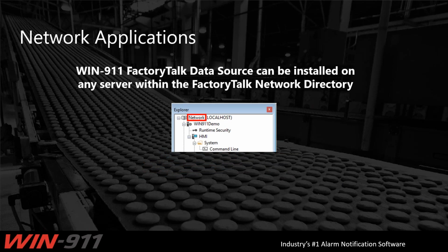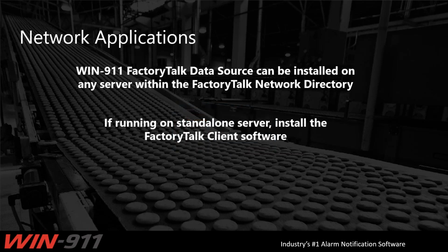If you install WIN-911 on a standalone server, so you install WIN-911 by itself without the FactoryTalk software there, what you're going to want to do is install the FactoryTalk client software on this machine, because it puts all the backend services that we need to communicate with an alarm and event server on that machine. You also need it there to join the directory anyway. So when you are running WIN-911 on a standalone server, you need to join that FactoryTalk directory. Installing the FactoryTalk client software is just the quickest way to get all the alarm and events backend stuff that you need on that machine to get it connected. You do not need to license this client software. You just need to put it on that machine. So that is some info about network applications.